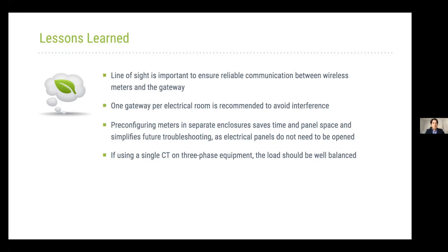Also, pre-configuration of the meters definitely helped reduce installation time and simplifies future troubleshooting efforts. If using a single CT on three-phase equipment, it's very important that the load is well balanced. If the load is not balanced, our recommendation is to use 3 CTs instead.